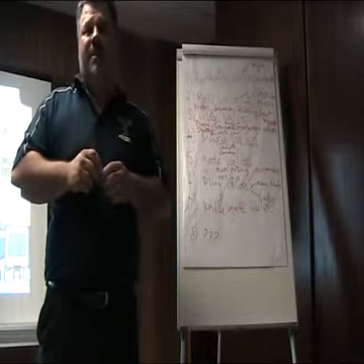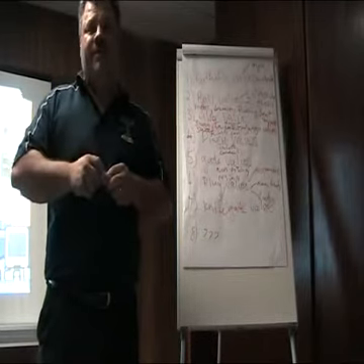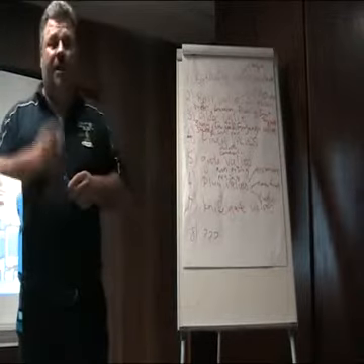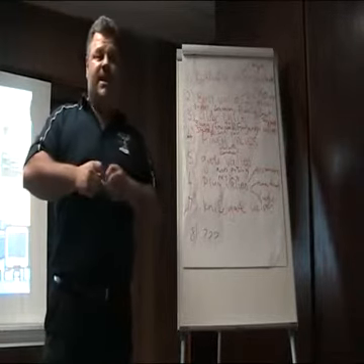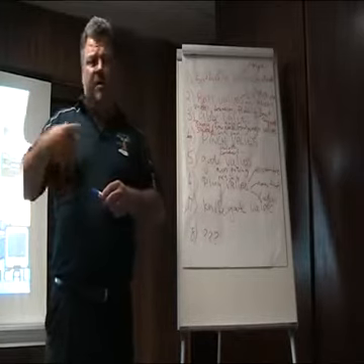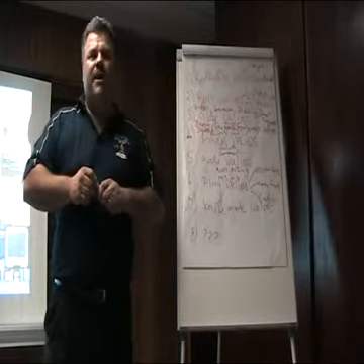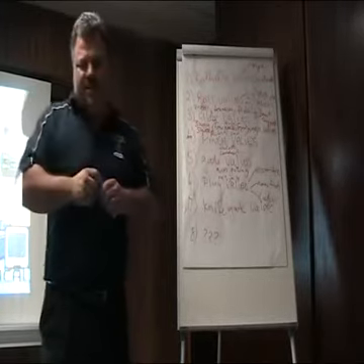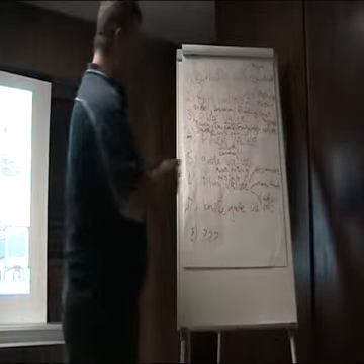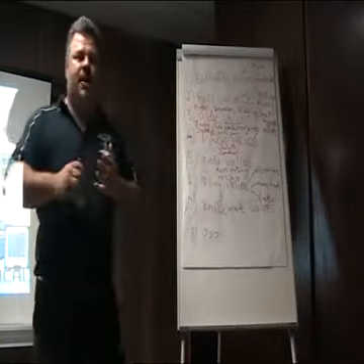When you've got a bit of solids coming down there and your trims are not hardened enough, you're going to have a leak rate eventually. But yes, a lot of people put in Stellite 6 valves years ago, which is now giving so many problems you cannot believe it. It's because of that. But that's detail.